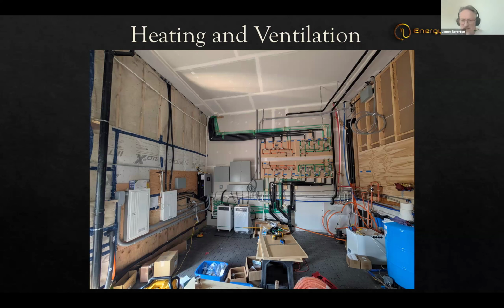Right beside that blue potable water tank there is a white phase change material tank from Sunamp. That's a phase change material tank that changes state at 58 degrees Celsius, and it also has a backup electric resistive element in it, which gives us backup for all our heating if we ever needed it. But we've got so many heat sources here that we're not really worried about it.